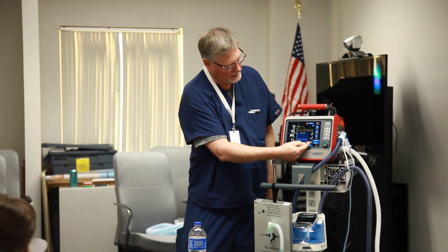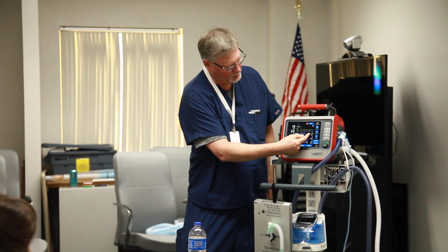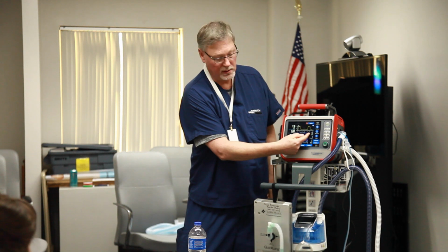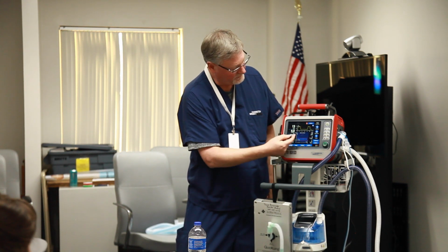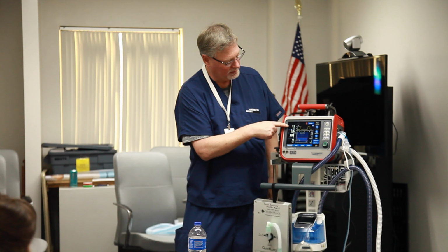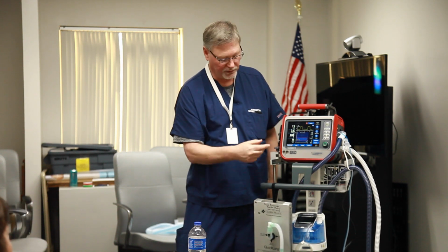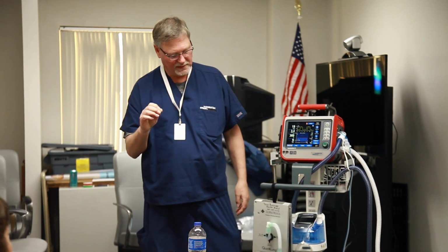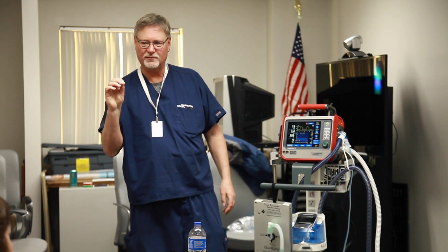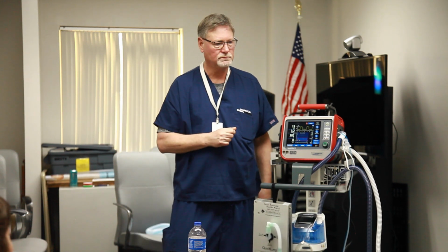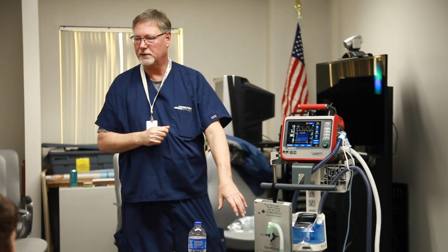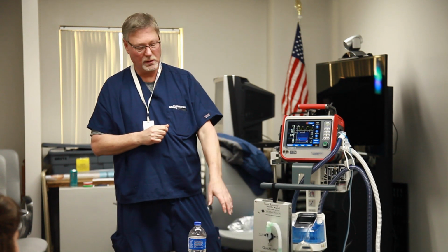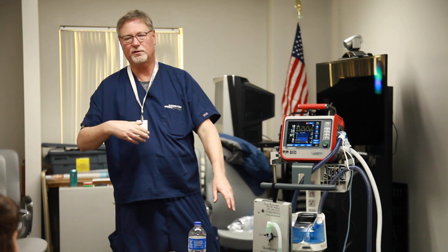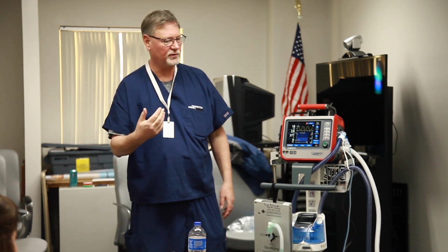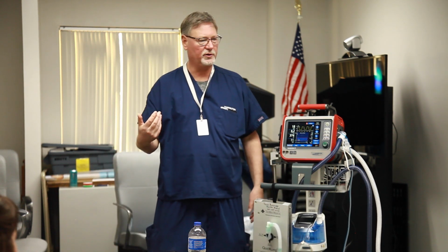This is how many spontaneous breaths. This is how many controlled breaths. That's the change in inspiratory pressure it's taking to deliver. So my peak pressure should be 12 and 5, should be about 17, 18 here, 19. There's always turbulence there. It always reads just a little bit higher on the peak pressure. But we're giving you exactly what's happening at that time at the patient. That's also doing the triggering for the patient. It's also doing the cycling for the patient. So it's not like they have to breathe through that whole circuit to trigger a breath either.